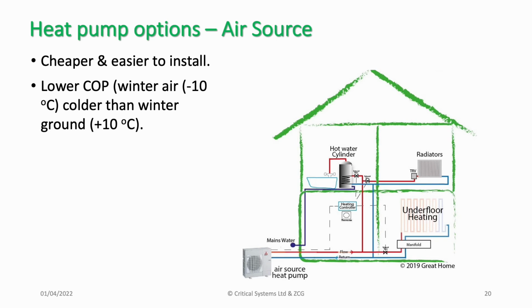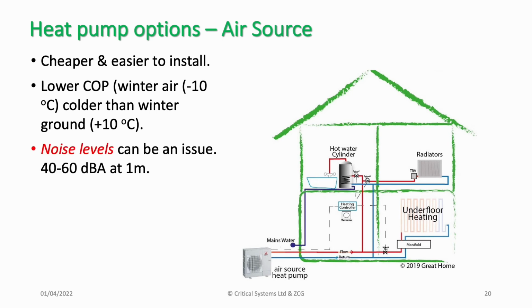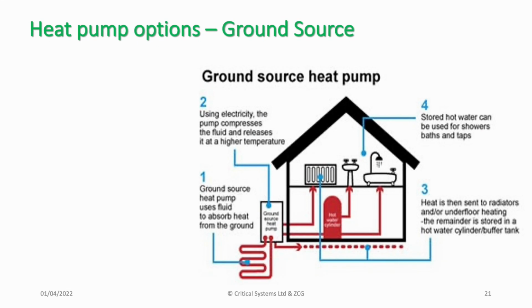They have a lower coefficient of performance than ground-sourced, because in the winter the air source temperature will be much lower than the ground temperature, could be -10 versus +10 degrees. Noise levels can be an issue, so I'd be very cautious if I saw a heat pump quoted at 40 to 60 dBA at 1 meter. This could be quite intrusive noise level. You need a location for the external evaporator, the air source. And you may need some planning permission in certain cases, depending where the device is located.